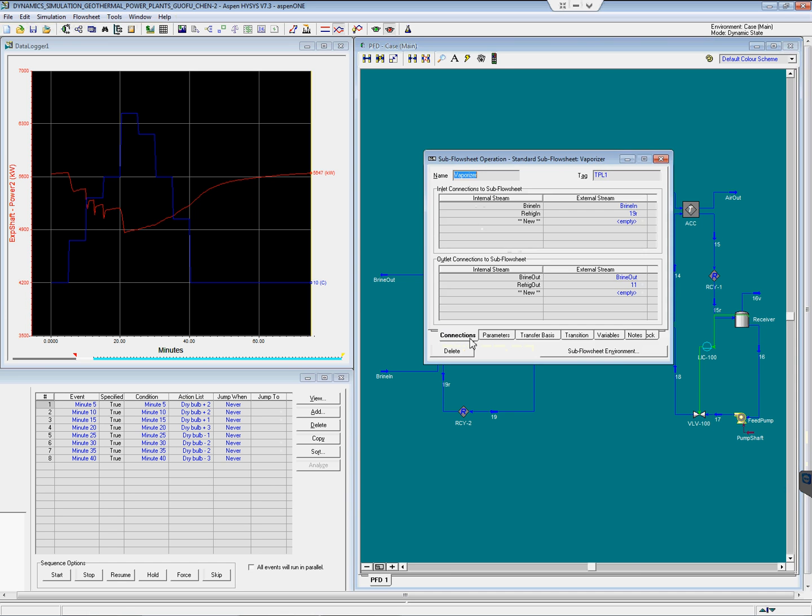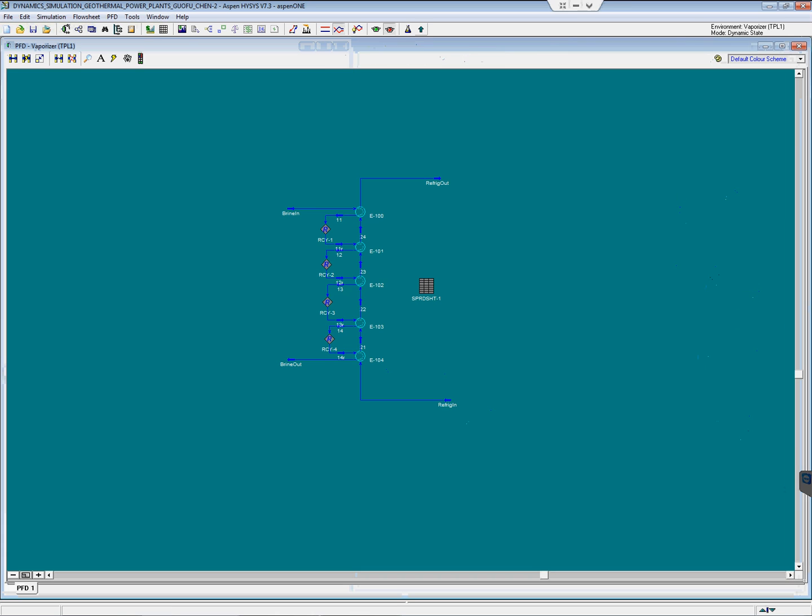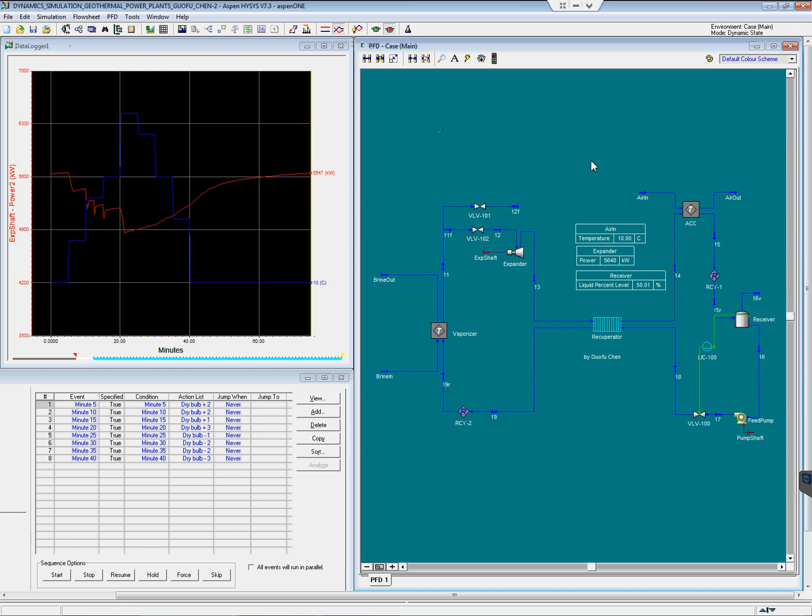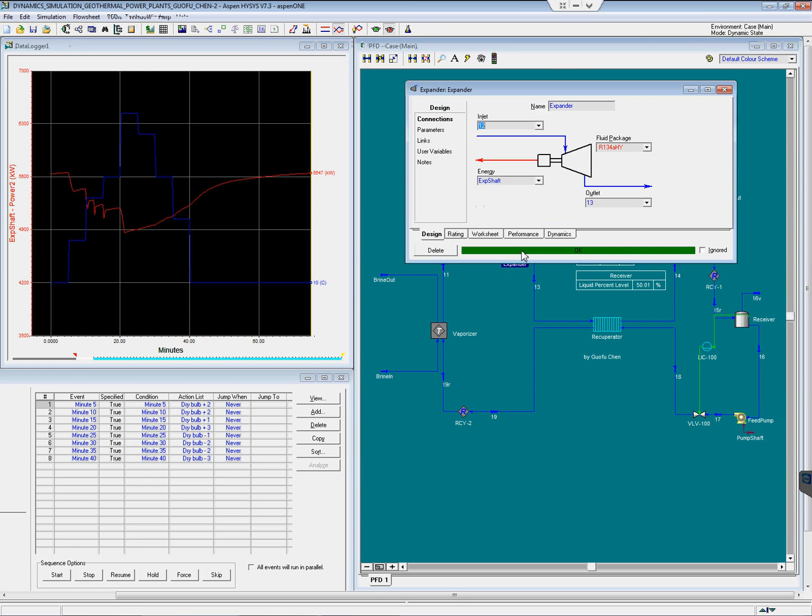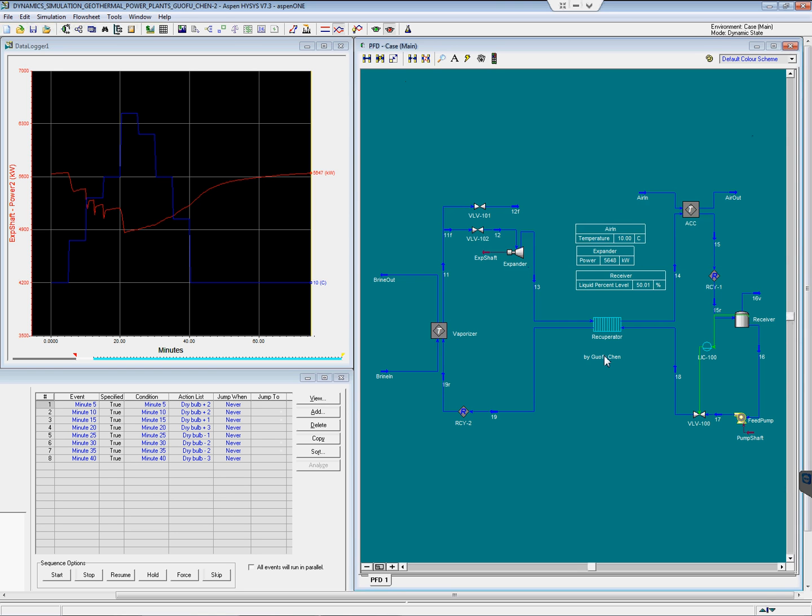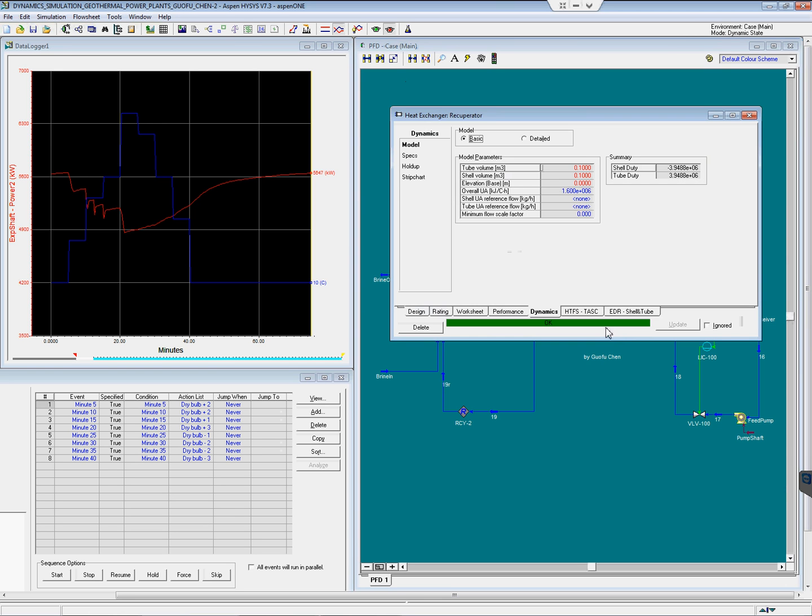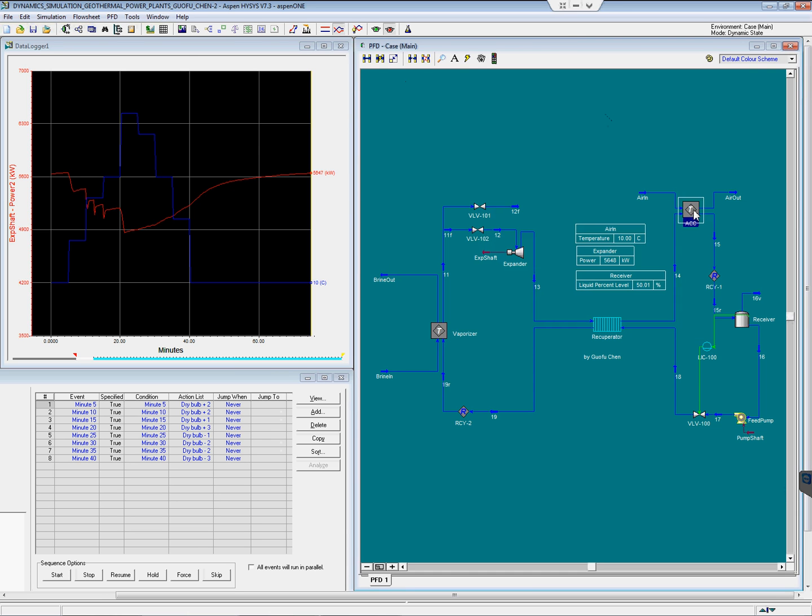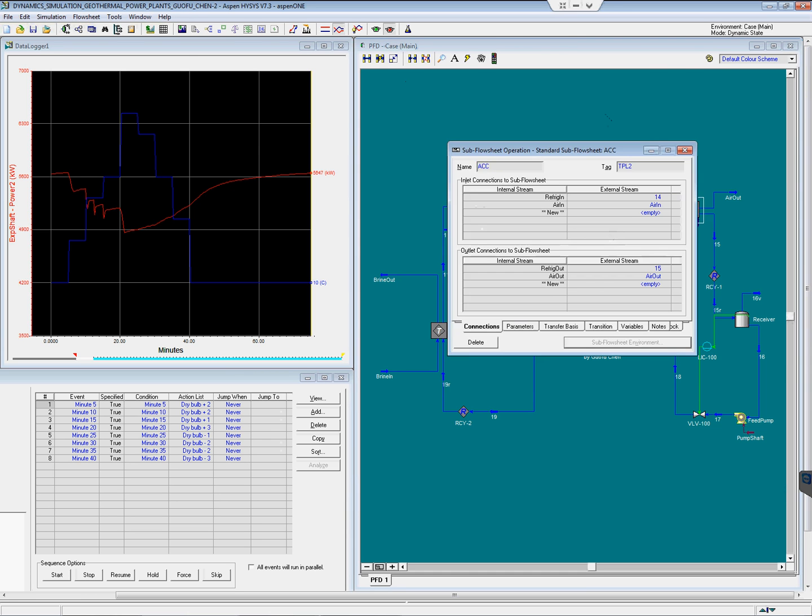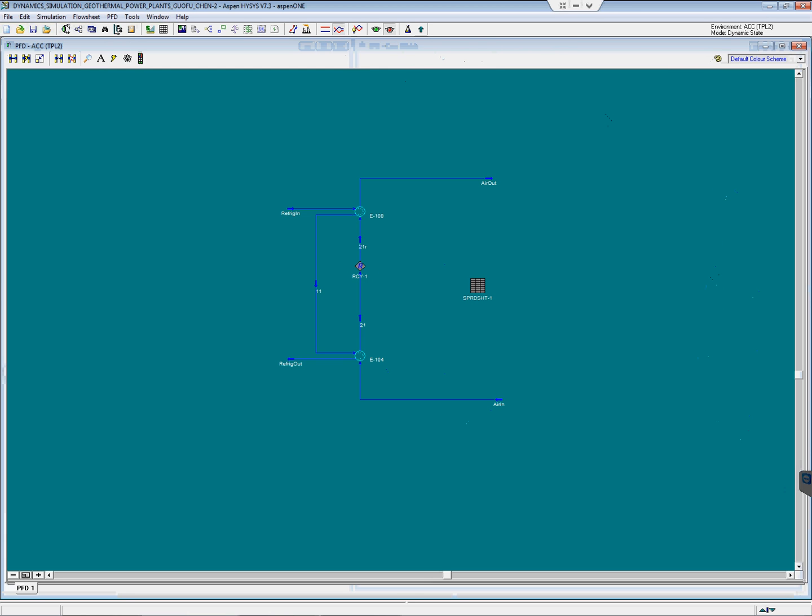The vaporizer is split into five sections to improve the calculation accuracy given a fixed UA. The expander is modeled with a fixed efficiency. The recuperator is modeled with a fixed UA. Air-cooled condenser is split into two sections to improve the calculation accuracy.